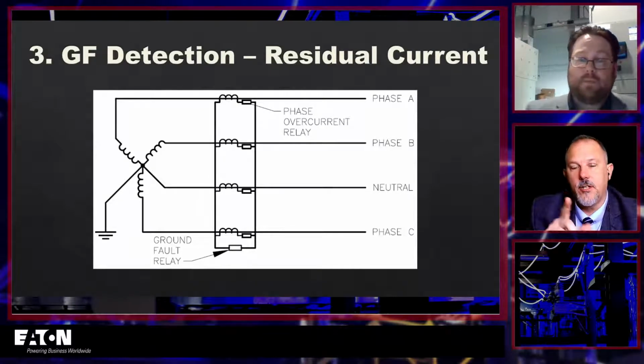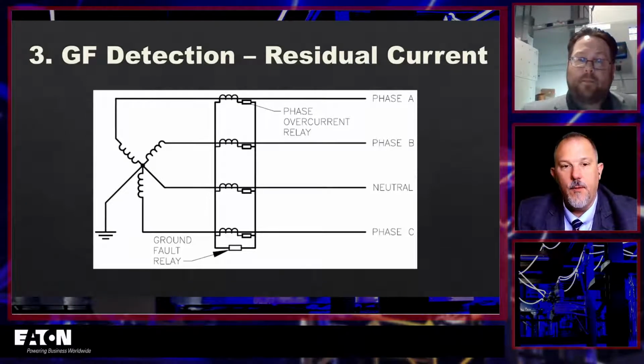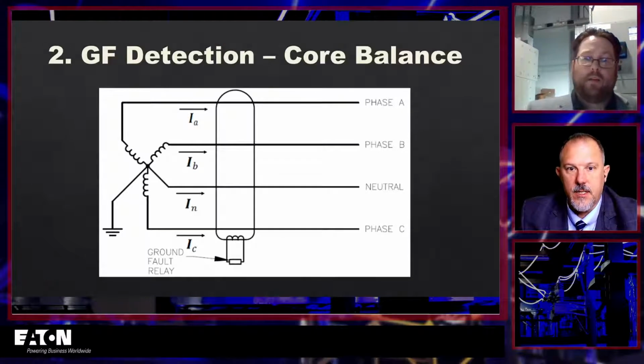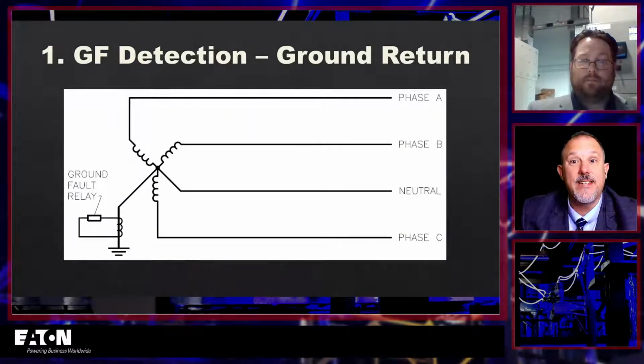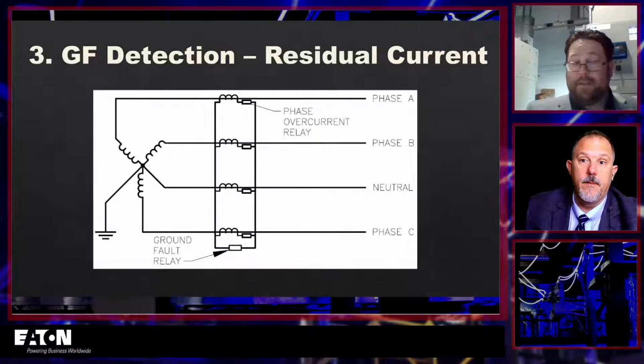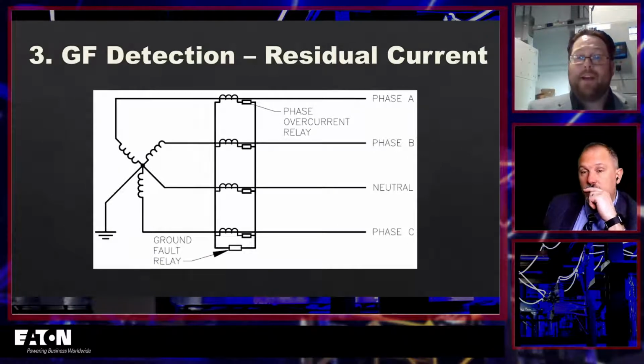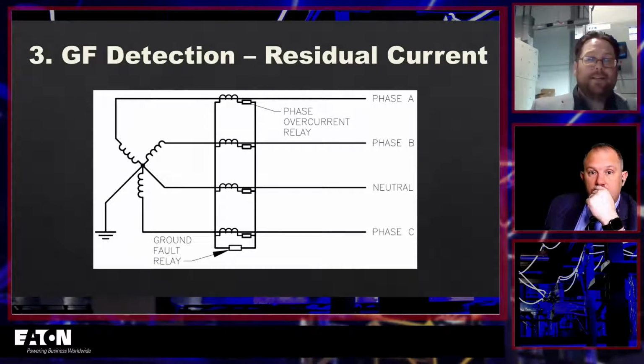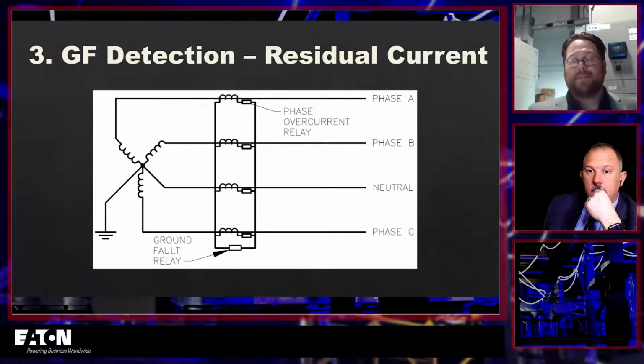Okay, so let me ask you a question. When you test this system versus this system versus this system, would you test it differently? Yes, you would. I mean, you have to, right? Because in the source ground scenario, you need to actually have current flow through that ground CT. That's what you're really testing versus the zero sequence and residual.